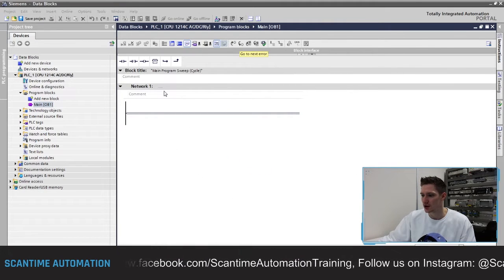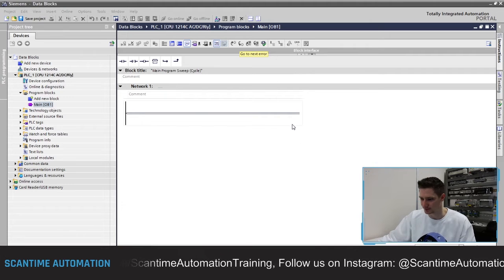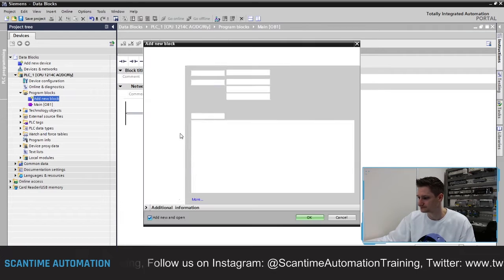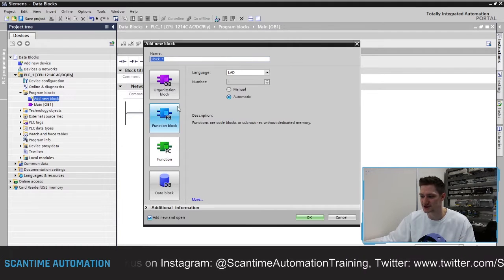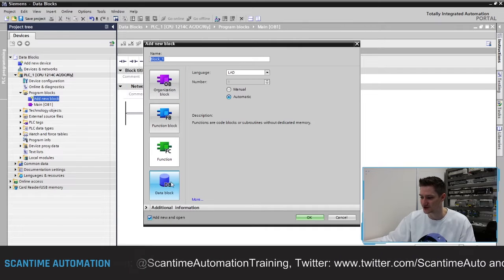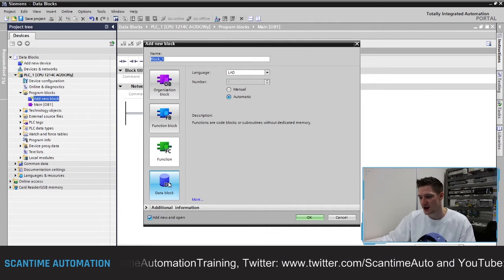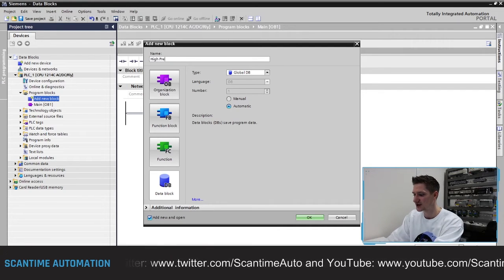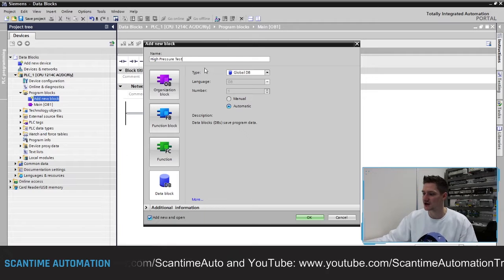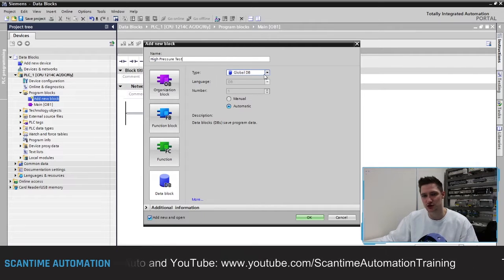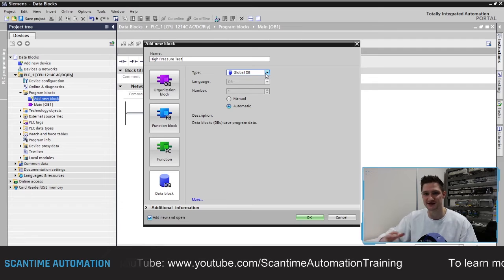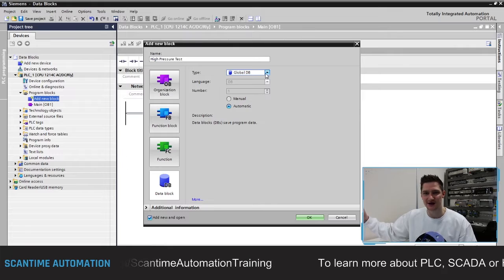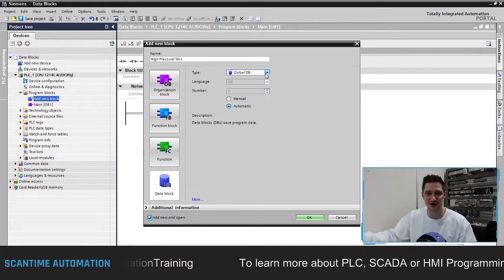Currently we are inside of OB1, the main block — just a blank program. If I go to 'Add New Block', we are given an option of what type of block we want to create. At the bottom left we can see 'Data Blocks'. If we select data blocks, we can give it a name — for example, 'High Pressure Test'. The type we'll use is a global data block, which means it can be accessed throughout the whole program, so any block inside the PLC program can send or receive information from it.